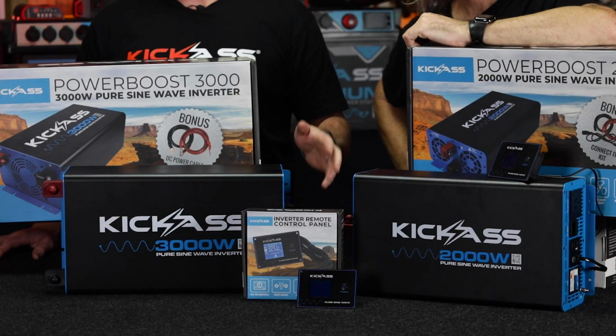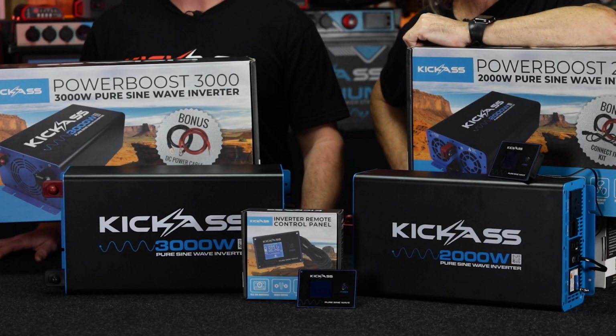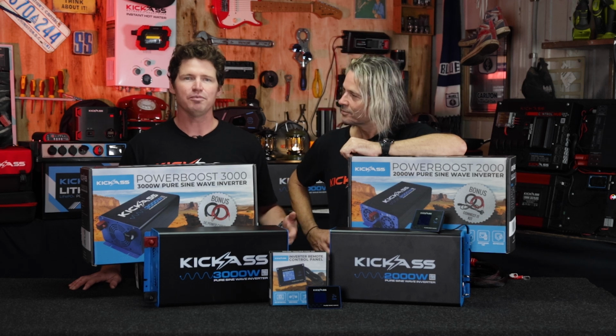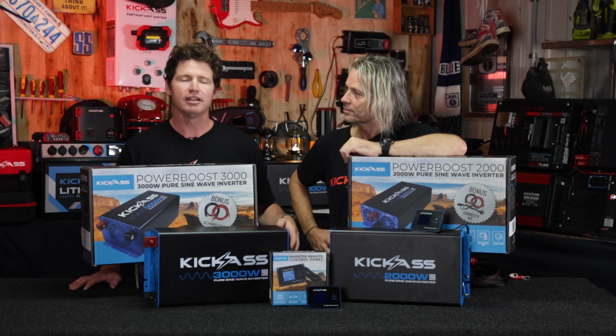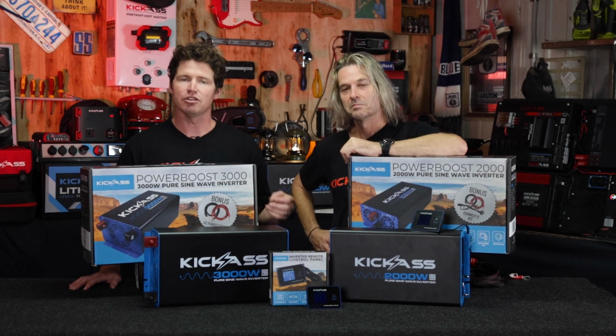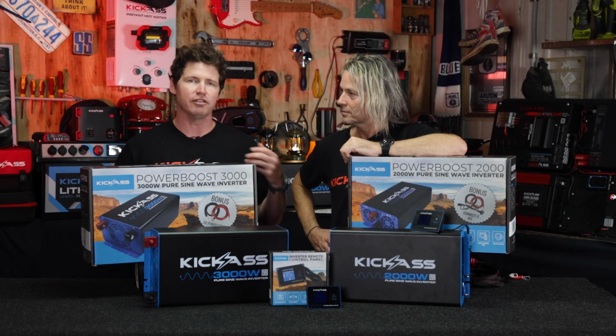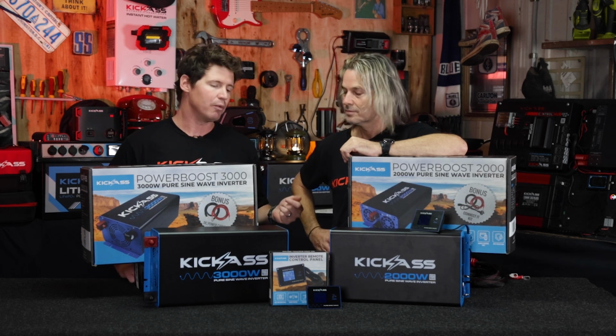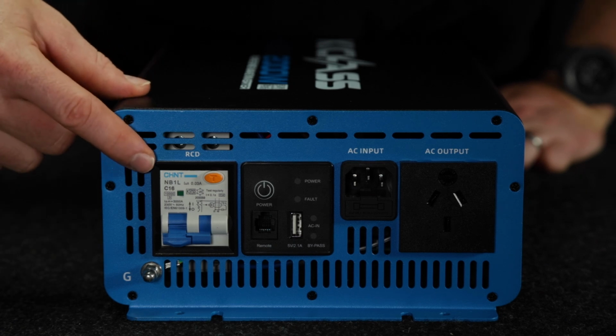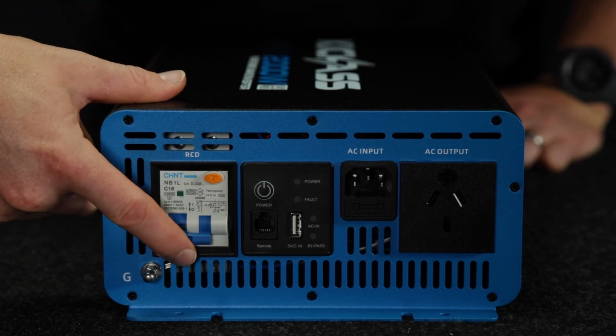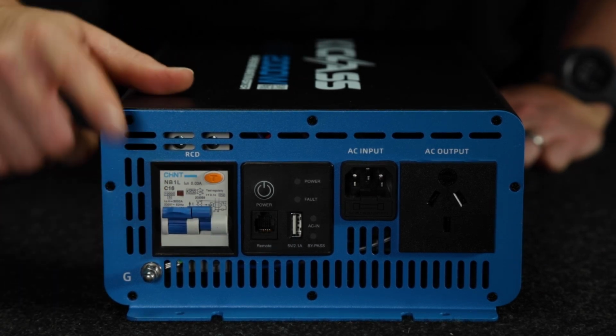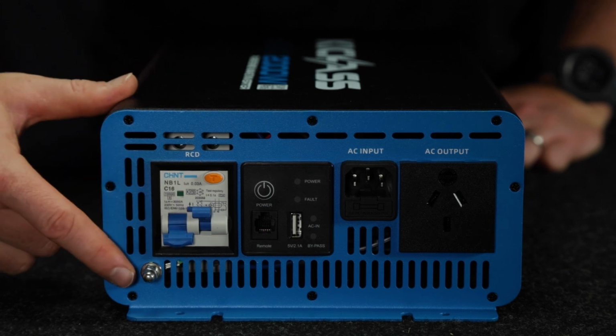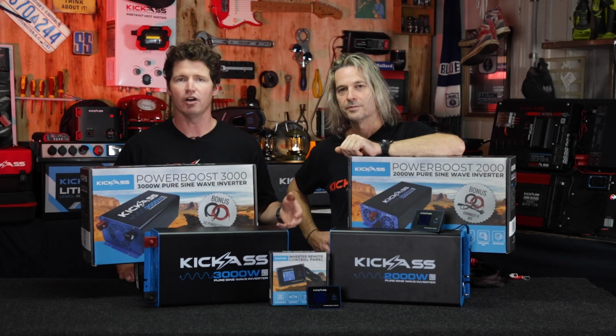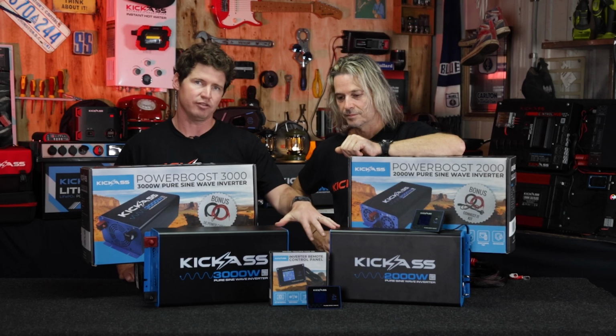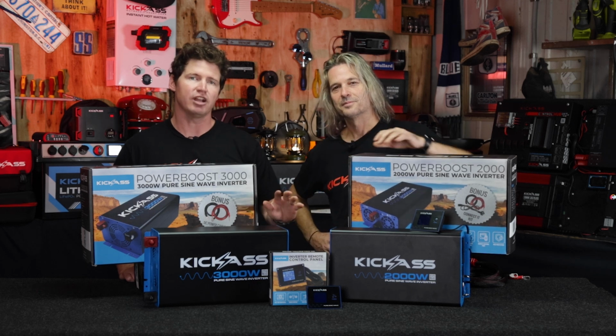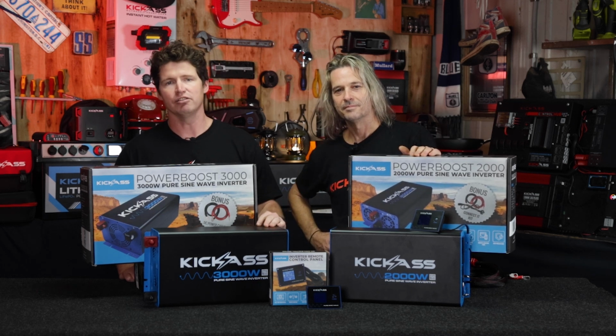So we've also got multi-level safety protection with these inverters. We have software control where we're monitoring input power, output power, and voltage. So if the device starts to operate outside the allowable conditions, it will shut down. But we also have an integrated RCD, that's a residual current device, and a circuit breaker, or RCBO. Some specific applications actually require this hardware device by law, so these devices are perfect for that setup. Software protection and hardware protection, great features of these inverters.